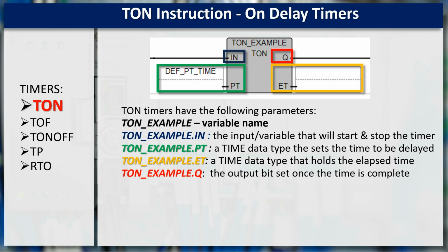Once the input IN is removed, then everything is reset. The elapsed time is cleared. We still have a program time, but the Q is turned off and the instruction is no longer functioning.